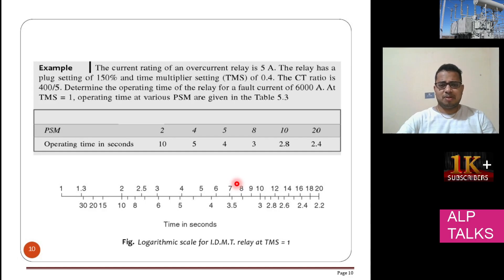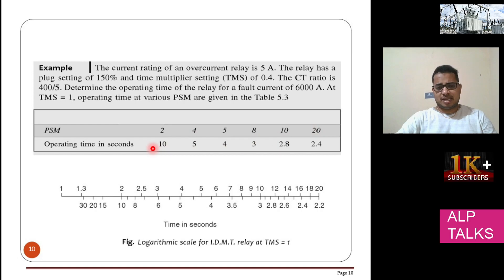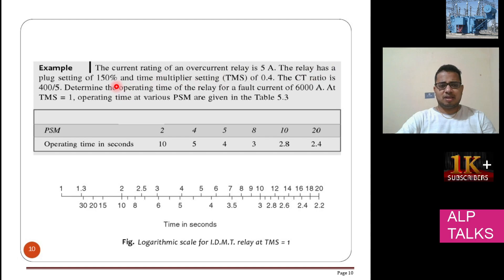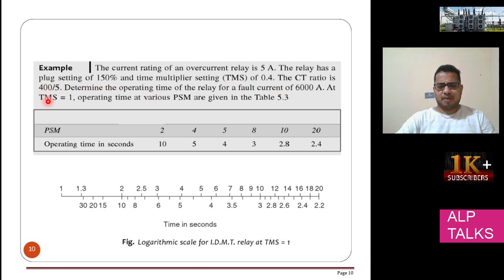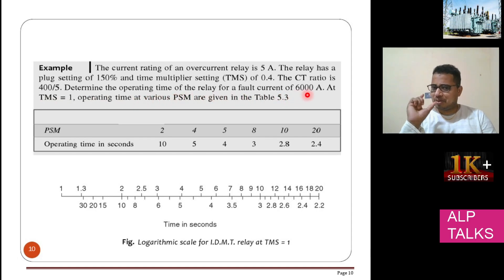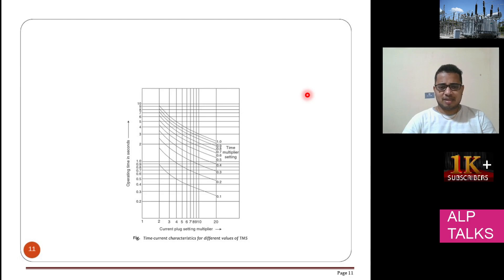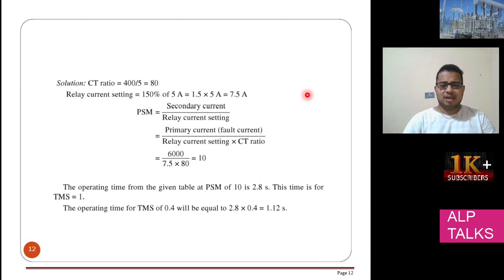Here is one example: the relay has a plug setting of 150% and a time setting of 0.4. We are using a CT of 400/5 amp. We need to determine the operating time of the relay for a fault current of 6000 amps. The CT ratio is 80, and 150% of 5 amps is 1.5 × 5 = 7.5 amps. So PSM = 6000 / (7.5 × 80) = 10. From the table, for PSM of 10, the operating time at TMS = 1 is 2.8 seconds.